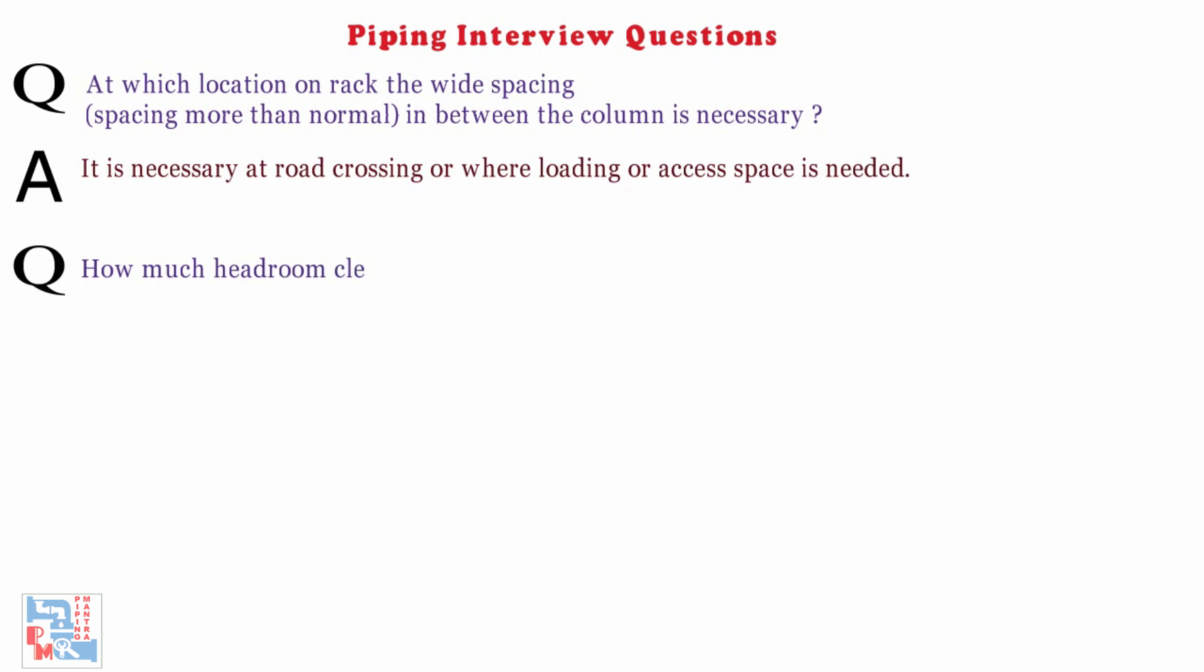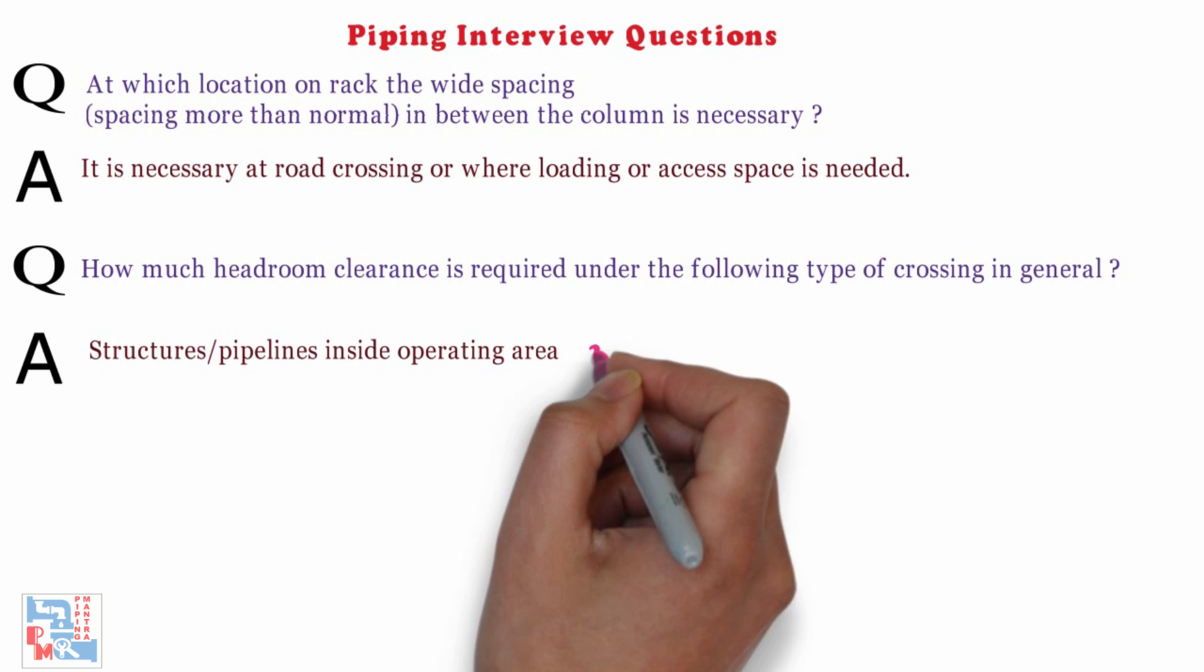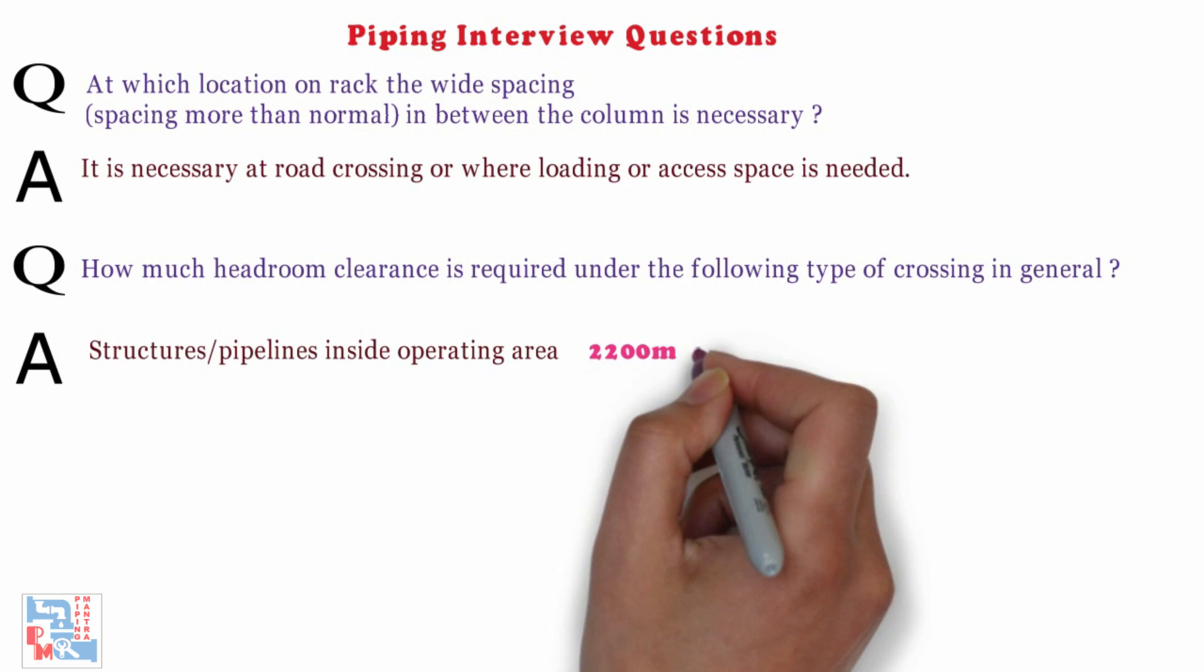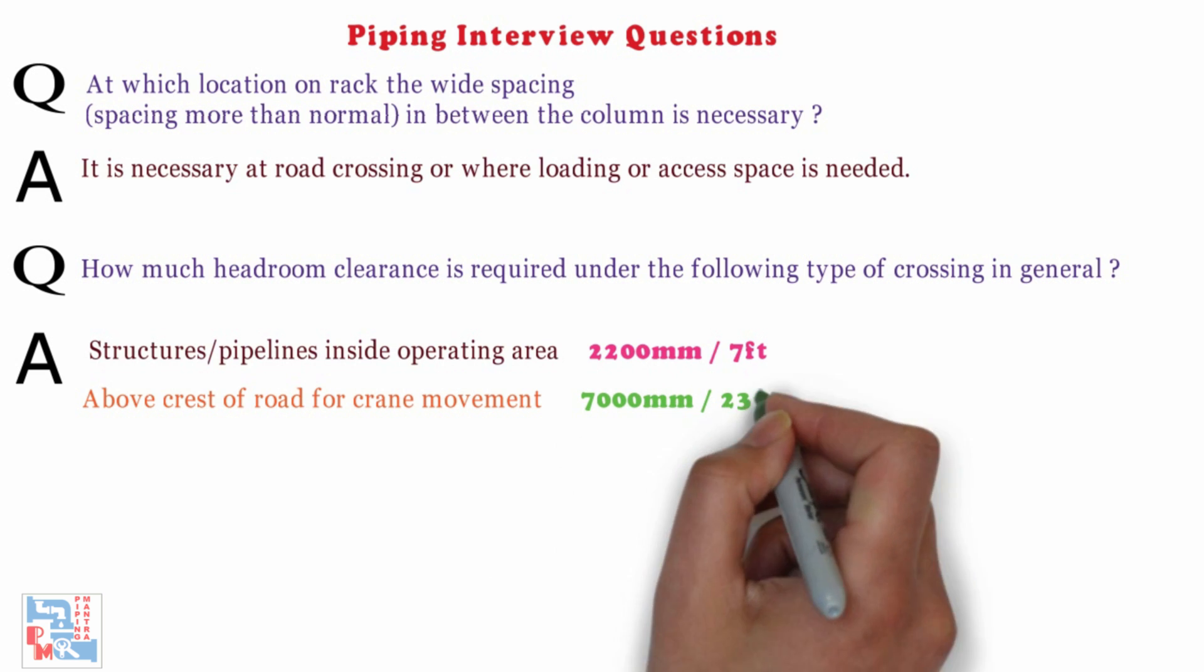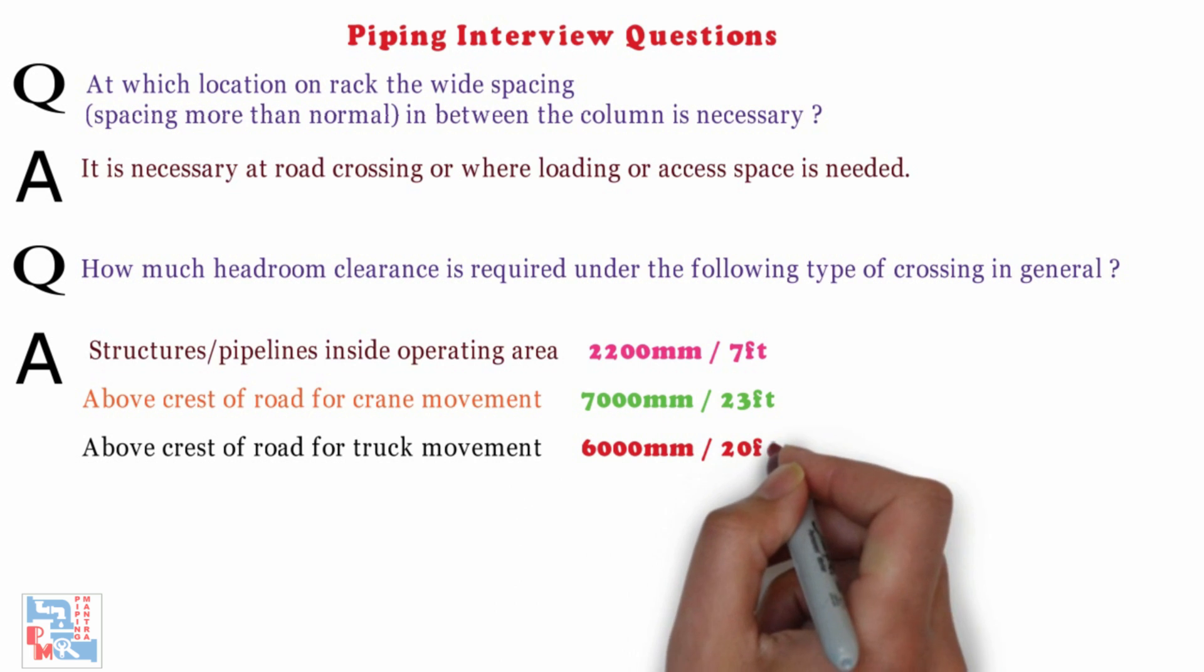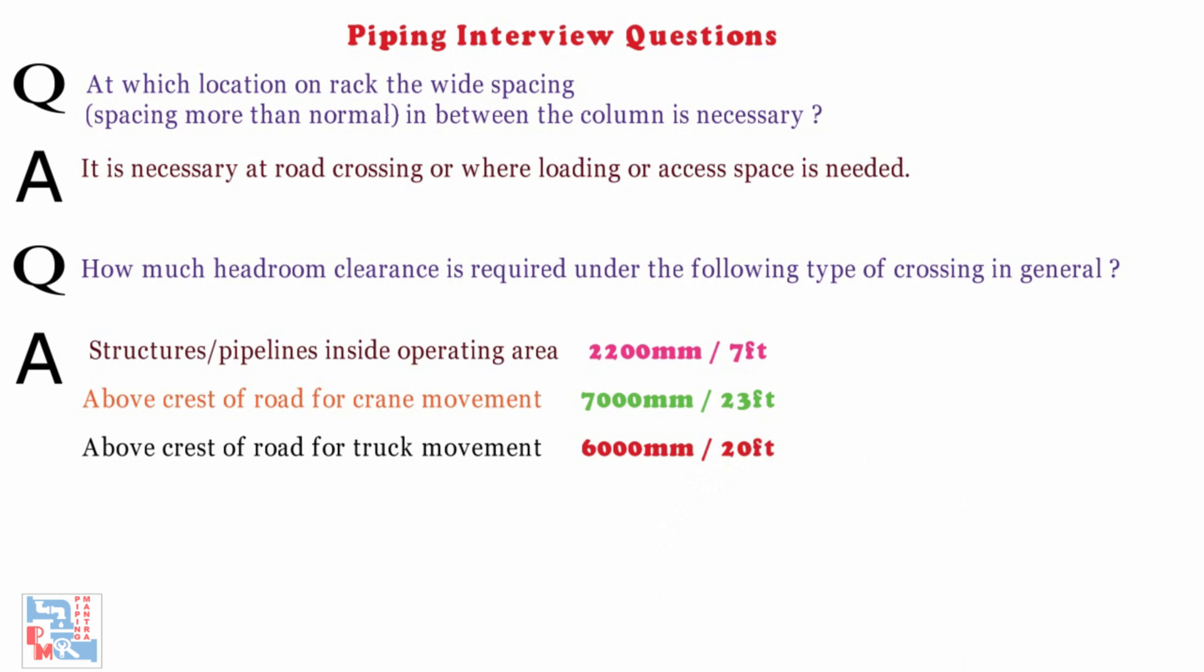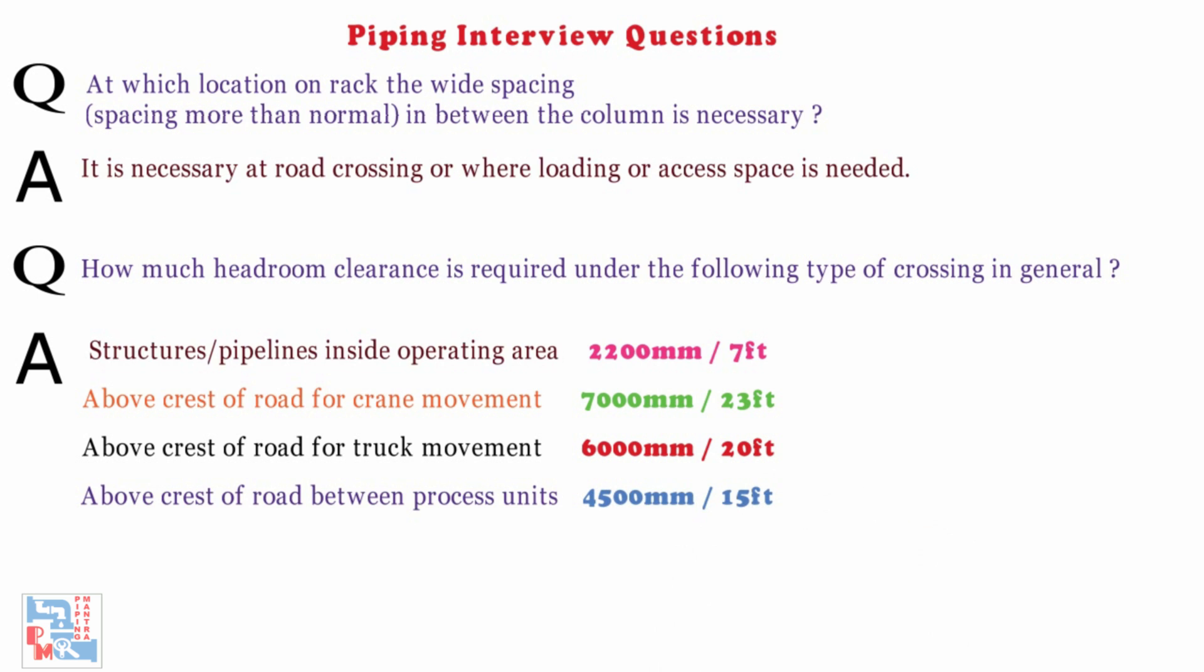Next, how much headroom clearance is required under the following type of crossing in general? The headroom normally provided is as structural or pipeline inside operating area requires 7 feet of headroom clearance or 2200mm. Above crest of road for crane movement requires around 23 feet or 7000mm of headroom clearance. Above crest of road for truck movement needs 20 feet or 6m of headroom clearance. Above crest of road between process units requires 15 feet or 4500mm headroom clearance.